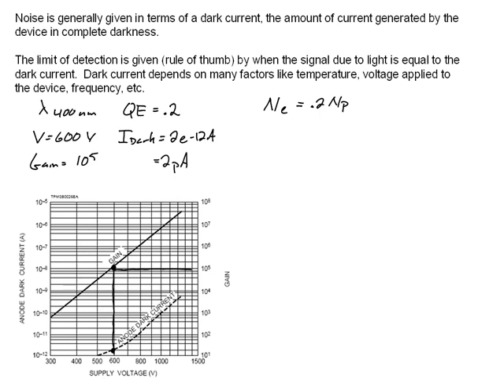And we know that the limit of detection, our dark current I_D, is equal to 2 times 10 to the minus 12 amps. And then if we divide this by the charge on an electron, 1.6 times 10 to the minus 19 coulombs, we find out that the number of electrons from our dark current is equal to 1.25 times 10 to the seventh electrons per second.